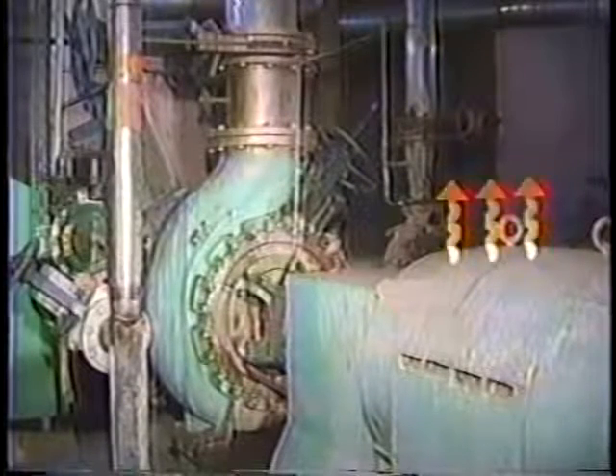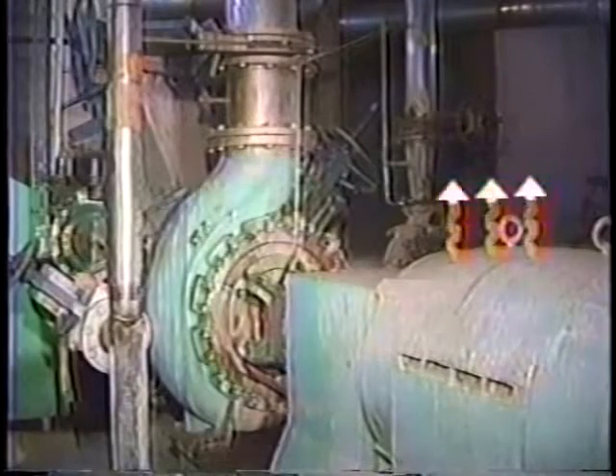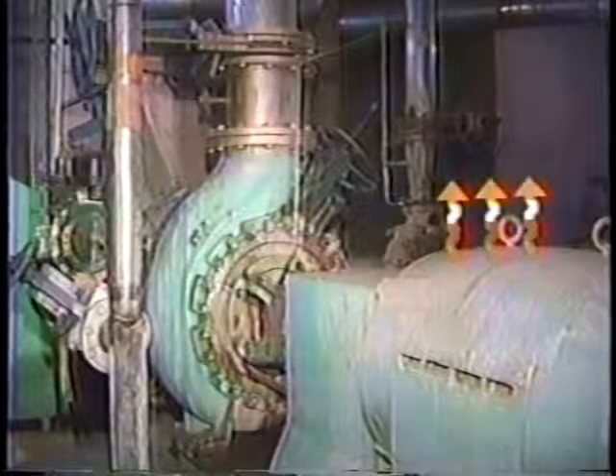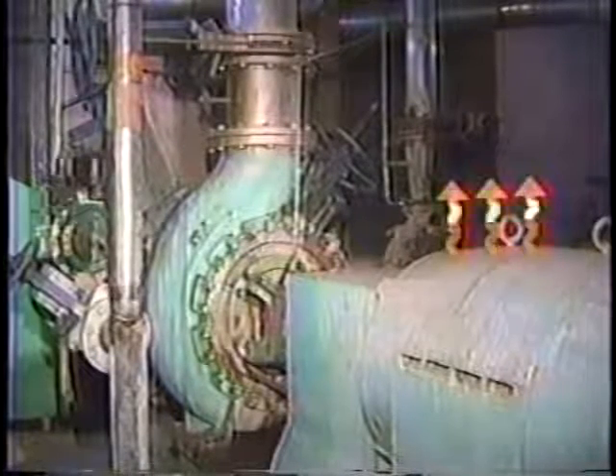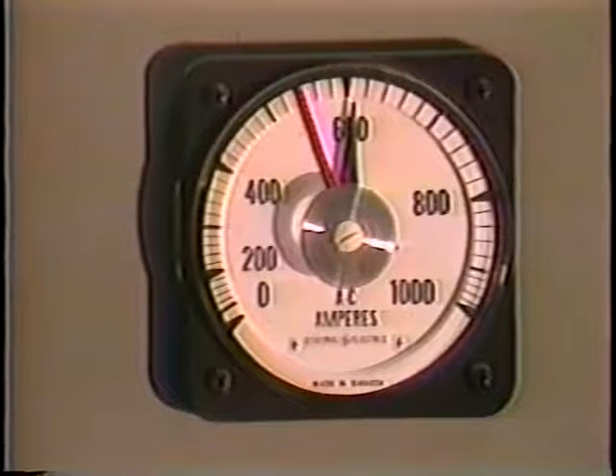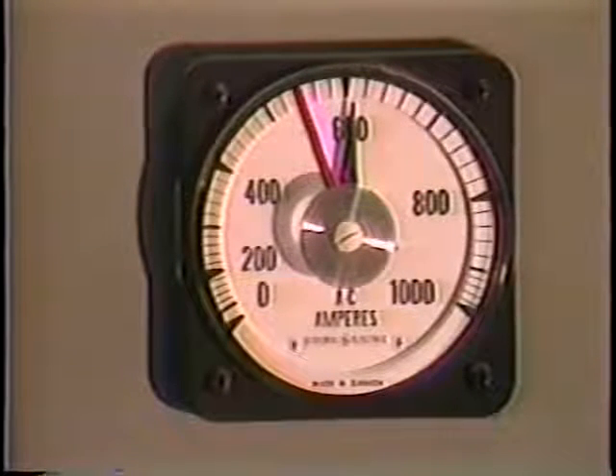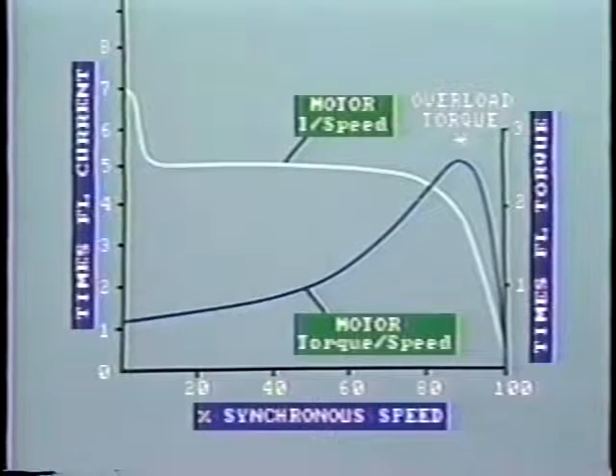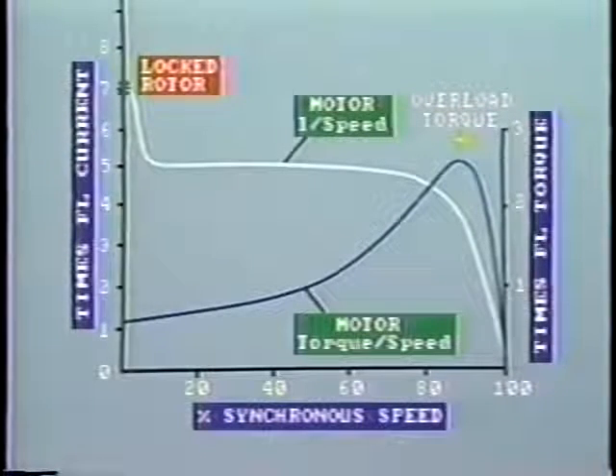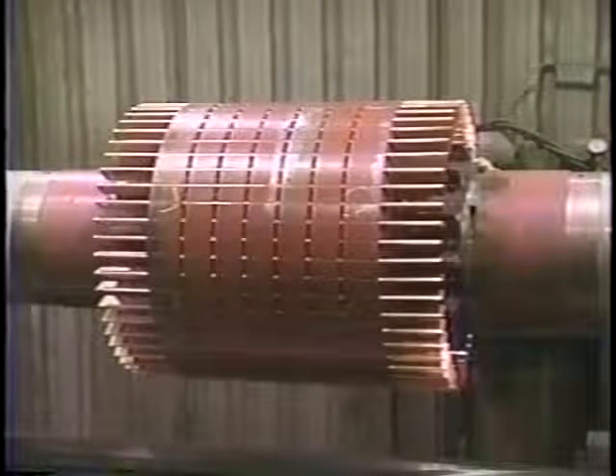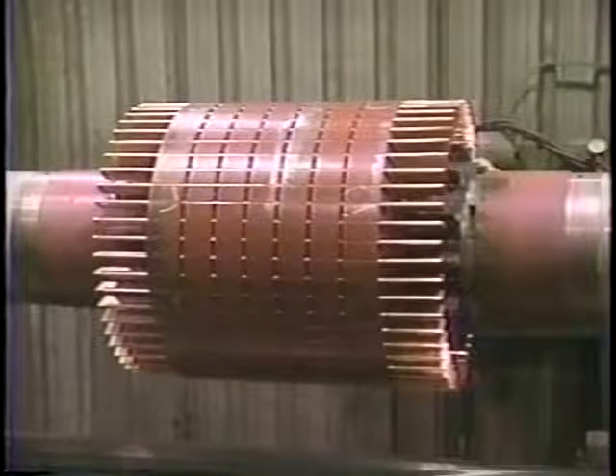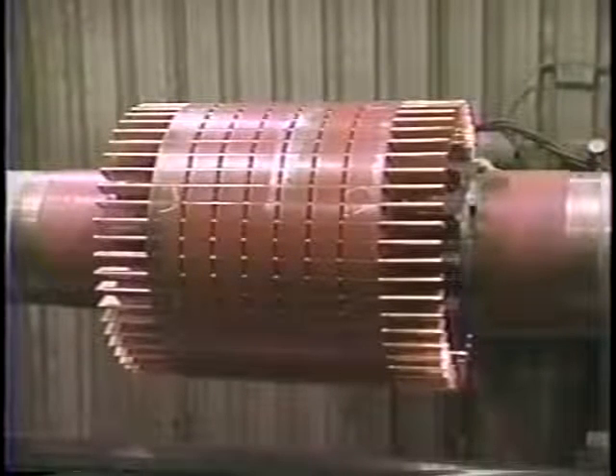Overheating may be caused by a variety of reasons. The obvious condition that comes to mind is that of overload, where the driven machine, say a fan or pump, is working above the motor's rated capacity. As we have already learned, this leads to considerable increase in current flow through the stator, which causes overheating if the condition is allowed to persist. If the overload is very great, perhaps due to a mechanical defect, then the motor will stall. This is known as the locked rotor condition. The stator current increases to a high value, perhaps 7 times normal rated current. This condition can cause severe damage to the rotor and stator windings within a very short period of time because there is no cooling with a stationary rotor.